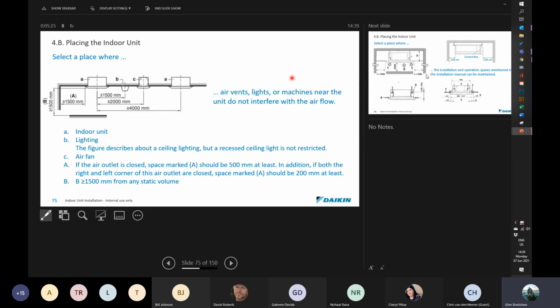Inside the installation manual that we supply, take note of the dimensions given for a correct installation, pertaining especially to minimum distances away from objects. These are very, very important. We often come across units that are installed with obstacles in front of the airflow, and this only causes the air to short circuit and not to be able to cool down the entire room. So things like air vents, lights, machines near the unit must not interfere with the airflow.